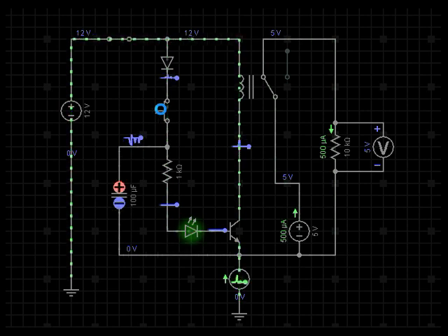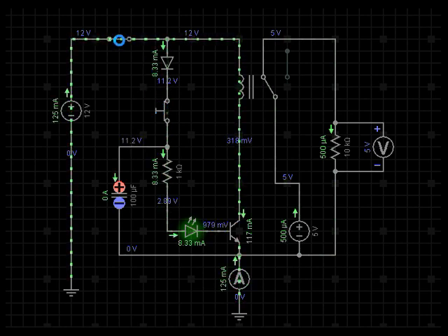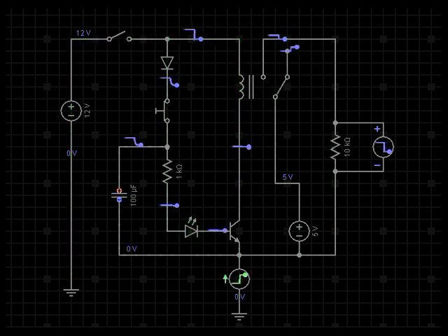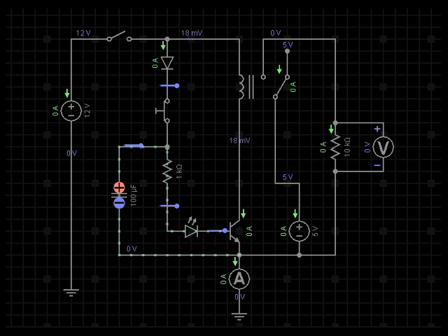In and out, we continue to simulate dirty track until at such point that the block occupancy is now unoccupied and the circuit is finished. The relay drops out. We have 0 volts on the control circuit, and the capacitor filtration circuit that we have in there continually degrades, but you'll notice it does not turn on the transistor.